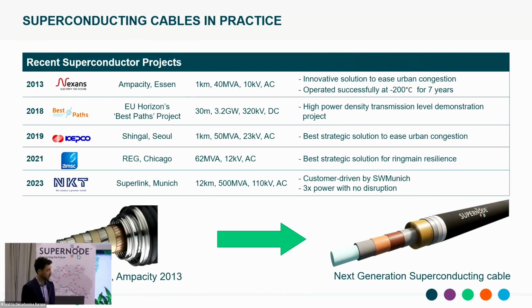Superconducting cables are not new technology per se. There are numerous examples operating very safely in power grids around the world. Probably the most prominent in Europe is the Ampacity project delivered by Nexans in Essen, Germany, which ran for 7 years. It was a 1 kilometer length, 40 MVA, 10 kV AC system.